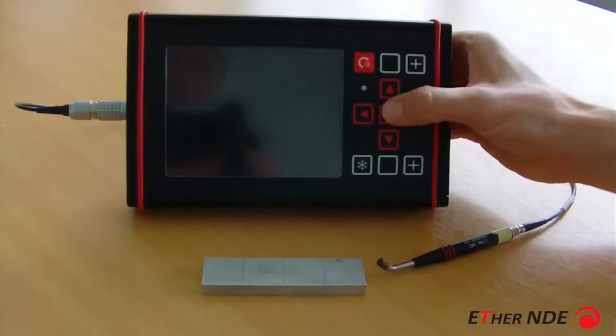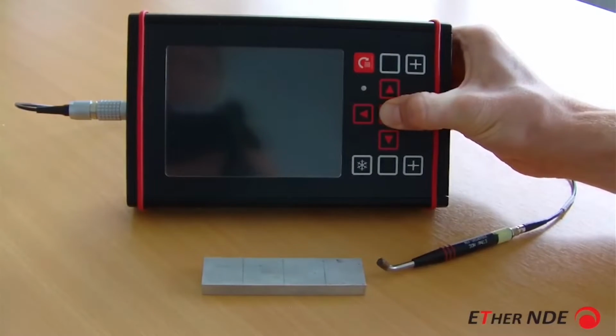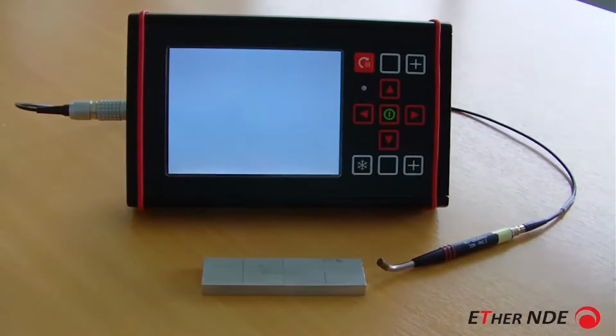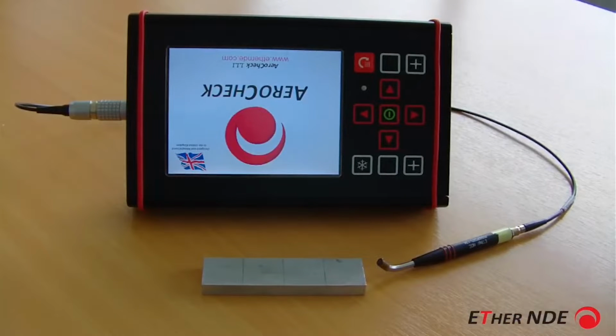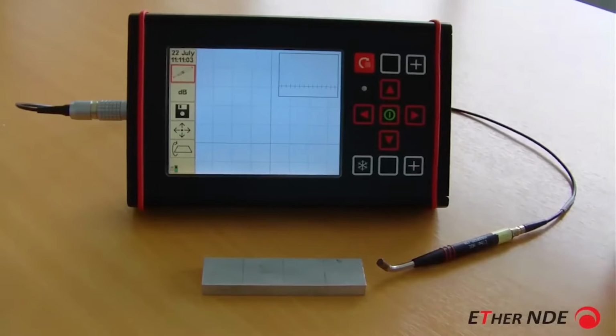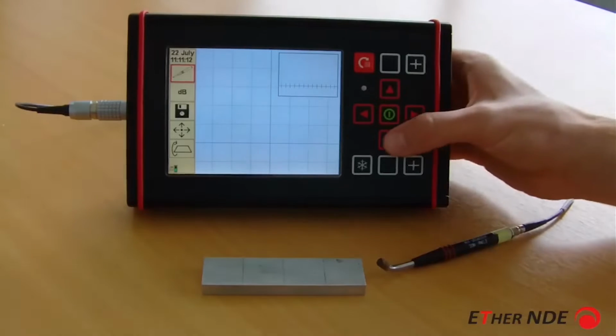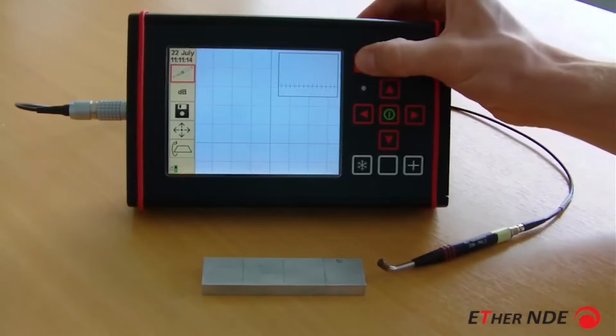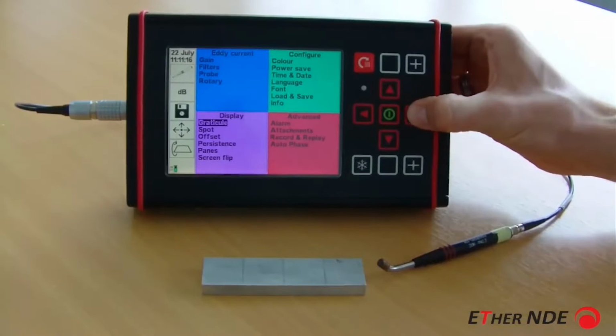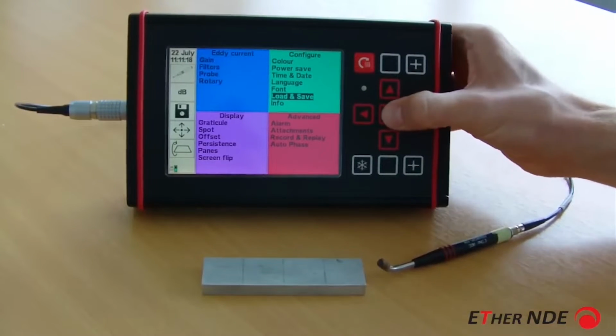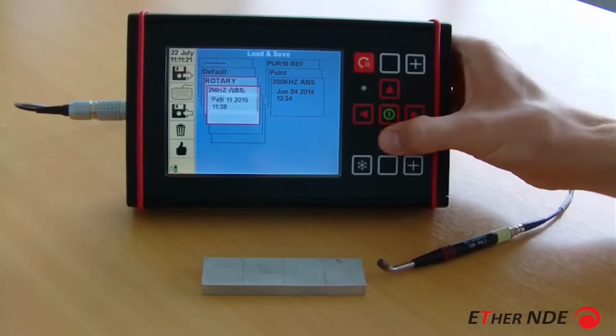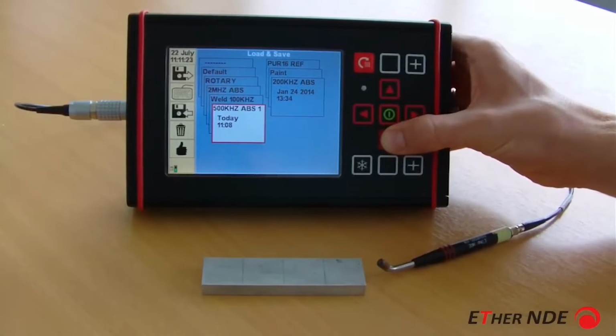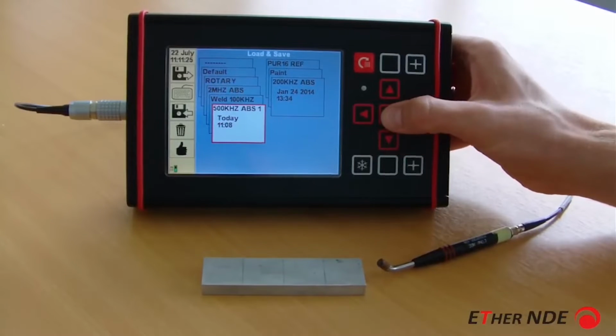So I shall begin by turning the instrument on. You'll see the splash screen is upside down, but again the instrument soon corrects itself. Okay, so the 500 kHz absolute setting is one of the default settings on the instrument. So if we go to the menu, you can go to load save. If I scroll down, we have a 500 kHz absolute setting.